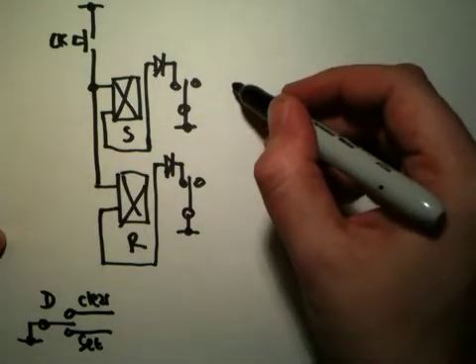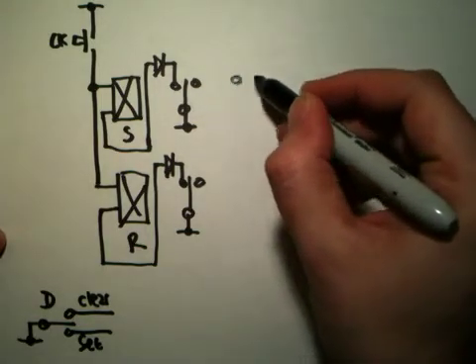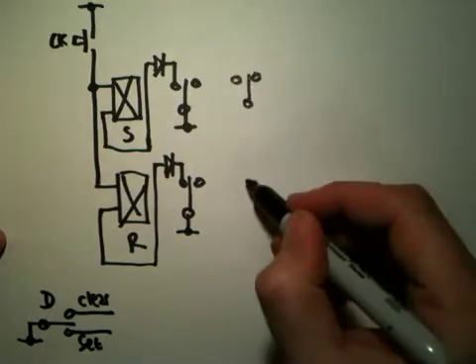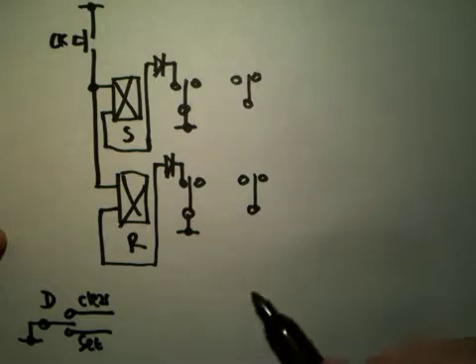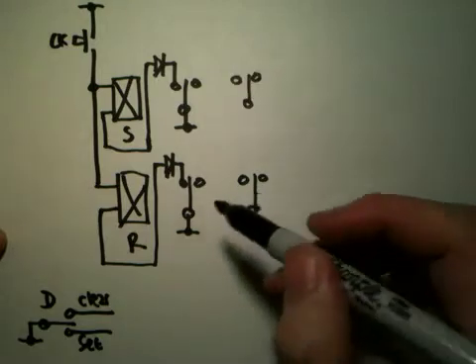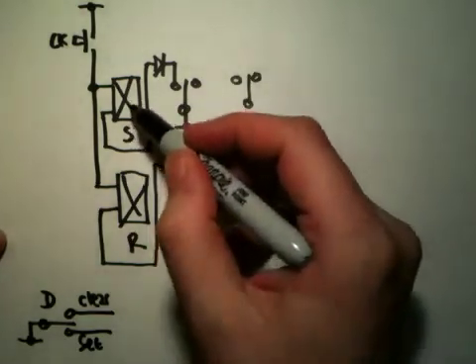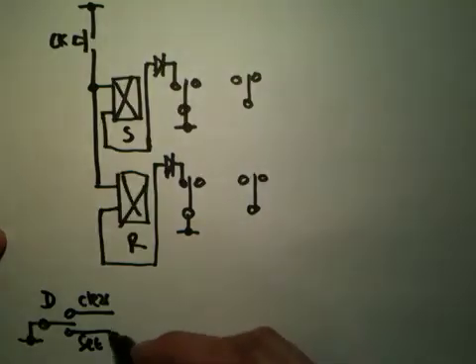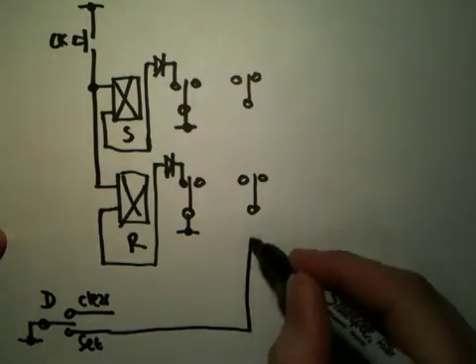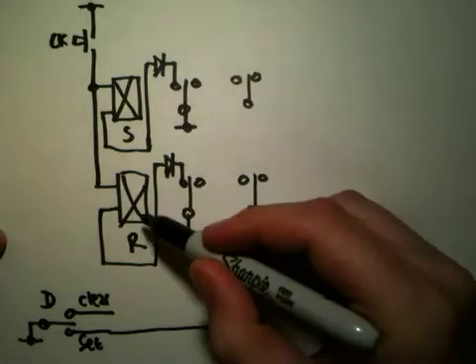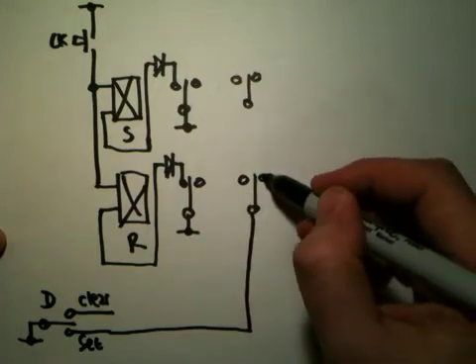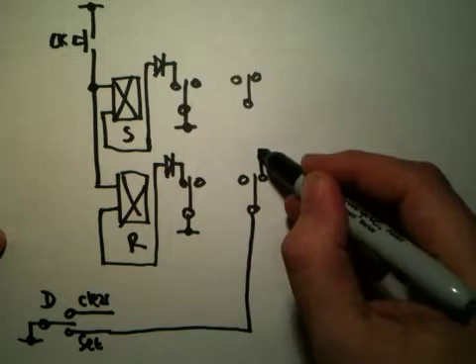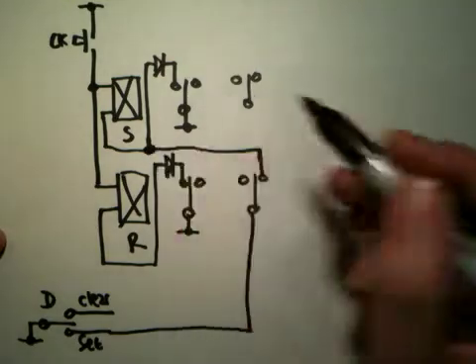Part of the way that we actually do this is that we have a separate set of contacts on here and on here. And so, when we actually want to set the set relay, this set input actually has to go through the contacts on the R relay first. And only if that one happens to be off is it allowed to come in and set the set relay like this.